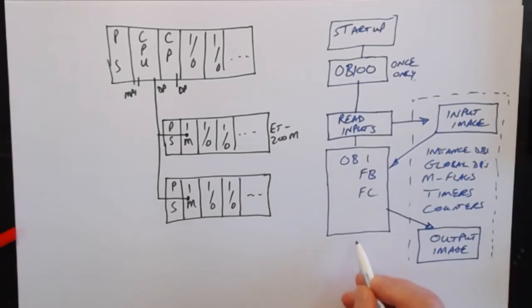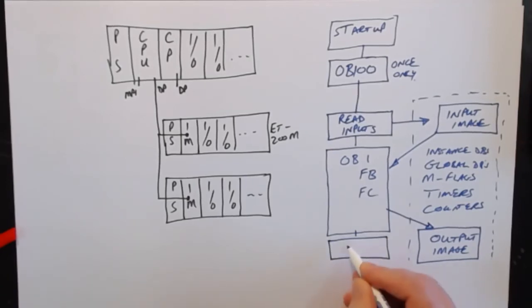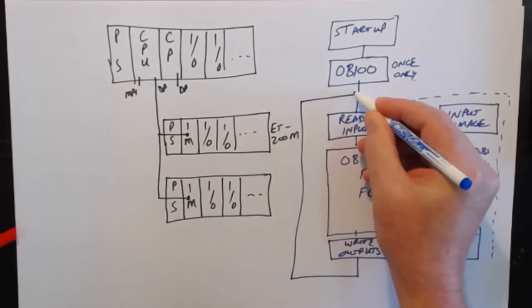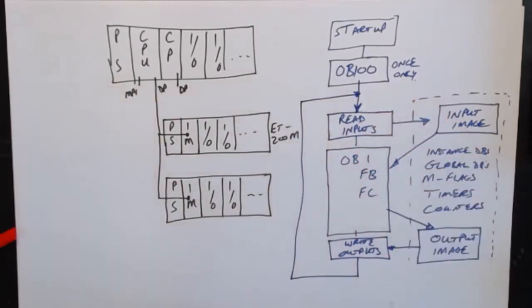And at the end of the cycle, when OB1 is complete, it then goes and does a write to the outputs, the physical hardware. It takes that output image, puts it on the hardware. Once it's done that, it then returns back to continue and repeat the cycle over and over again.